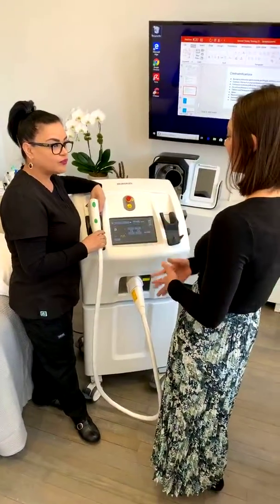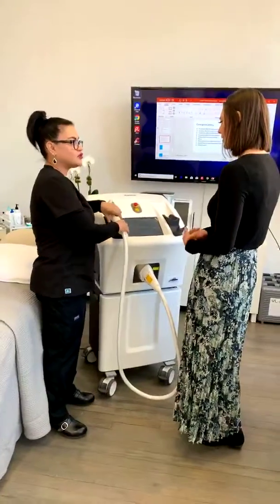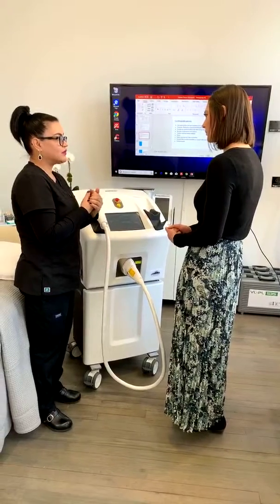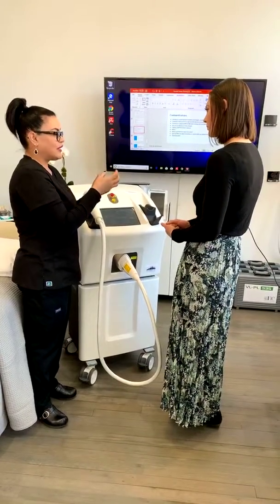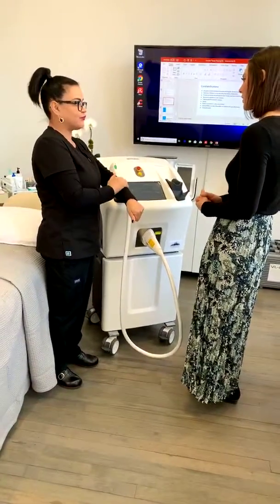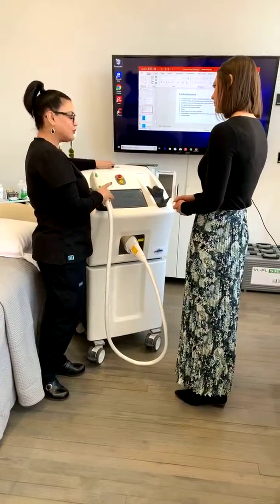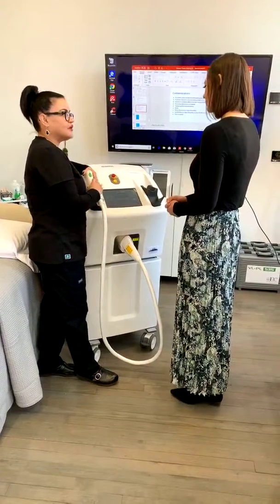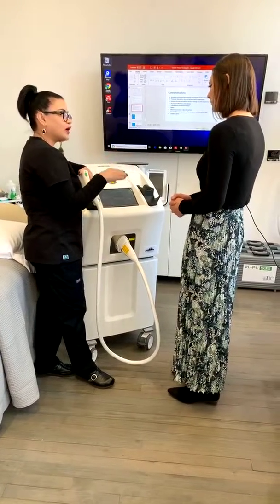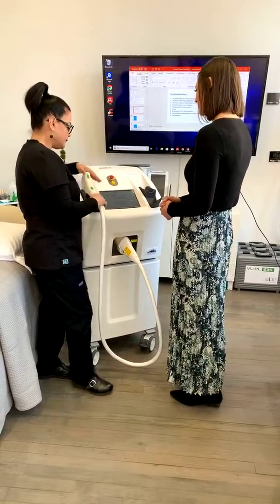So why wouldn't you just leave it on all the time, even for vascular? The system automatically shuts it off. Let's say you're going to give me a vascular treatment. The coldness is going to make the vessels retract, and we don't want that. We need them right on top to get rid of them. And the same thing will happen with the dark spots. You're only going to find with vascular and pigmented lesions that the coolant doesn't go on. But if you want to, you have the option, obviously, to put it on low. Okay?